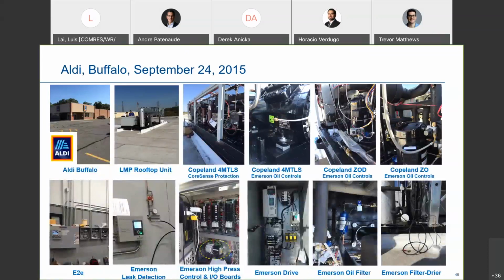Those of you who were on the WebEx Friday morning, Kurt covered some of this as well. But just to give you an idea that a lot of our products are installed out there. This happened to be an Aldi store in Buffalo, New York that I went to a few years back, where we've got our 4 MTLs. You don't see a sight glass there because it's on the other side of the compressor, 4 MTL. You've got your digital scroll with our OMB oil level control. You got a fixed capacity scroll.